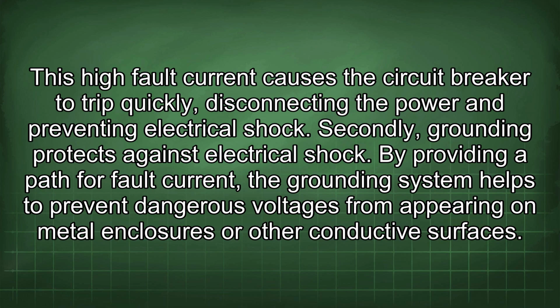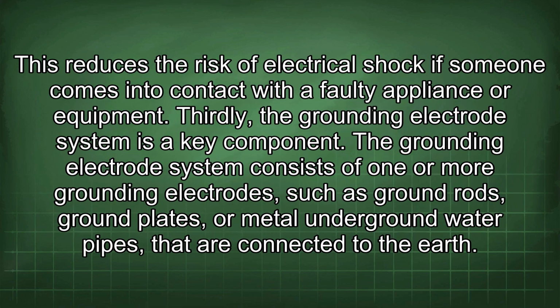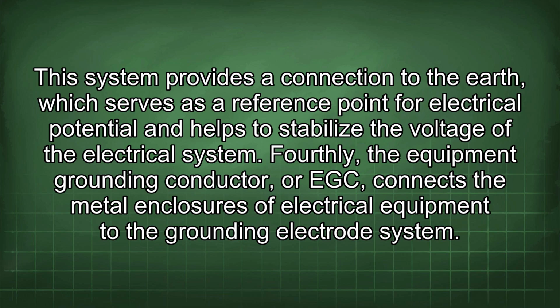Secondly, grounding protects against electrical shock. By providing a path for fault current, the grounding system helps to prevent dangerous voltages from appearing on metal enclosures or other conductive surfaces. This reduces the risk of electrical shock if someone comes into contact with a faulty appliance or equipment. Thirdly, the grounding electrode system is a key component. The grounding electrode system consists of one or more grounding electrodes, such as ground rods, ground plates, or metal underground water pipes that are connected to the earth. This system provides a connection to the earth, which serves as a reference point for electrical potential and helps to stabilize the voltage of the electrical system.